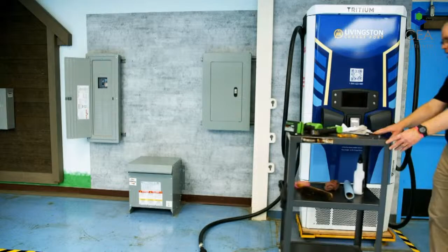Obviously, basic safety stuff. Because I'm working on the charger, I'm going to kill the power at my switchgear. If I had to work on the switchgear, we would go to the utility pole and break open our fuses. So I'm looking at it, figuring out what piece of equipment I want to work on, and I'm going to kill the power feeding into my transformer and fuse breaker box. Obviously, I'm going to confirm that the power is dead. I'll go through with my meter, take measurements, make sure it's dead before I put my fingers in there. All right, so basic safety there.